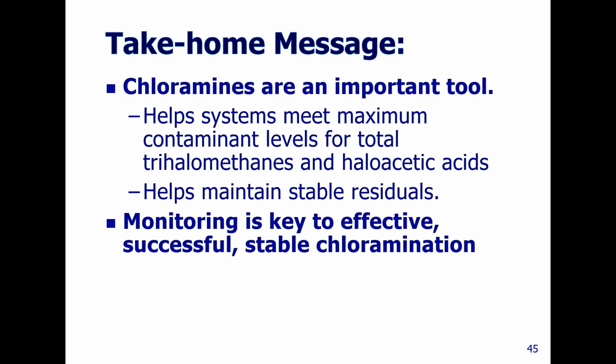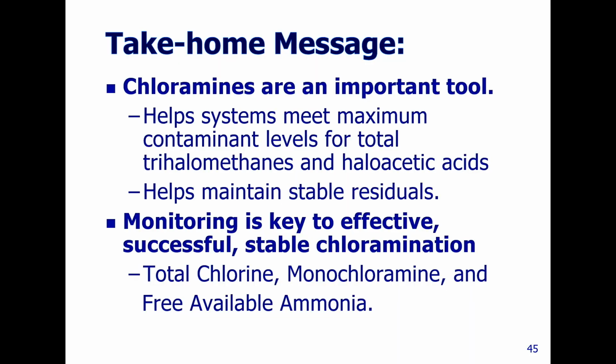And monitoring really is the key to success. If you're not doing it regularly and you're not looking at it for trends, right? A one-time snapshot might give you some idea, and all of a sudden you say, oh, I've got an issue. But you need that long-term trend to be able to look at it and say, oh, this is what's happening. So you can spot nitrification in the early stages when you can address it, as opposed to, oh, the whole system's boogered up. I like that word, boogered up. We want to look for total chlorine, monochloramines, and our Superman, free available ammonia, so that you know what's going on in your distribution system.